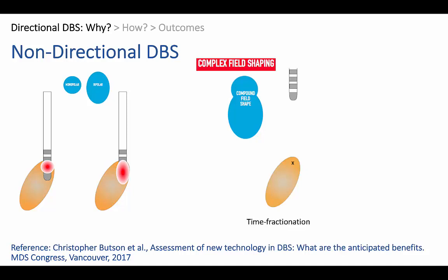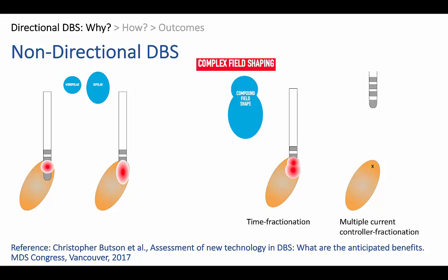We do this through two technologies. One is fractionation of these fields in time, which is similar to Medtronic's interleaving protocol. So you have two different programs running alternately at a very high frequency — 125 Hz — and that effectively produces that complex field shape that you desire. The second and newer technology is multiple independent current controllers, where you can have completely different programs on two separate contacts, fractionating current between those two contacts to produce a similar field shape. The advantage being that because you're not time fractionating, frequency is opened up as an extra parameter.